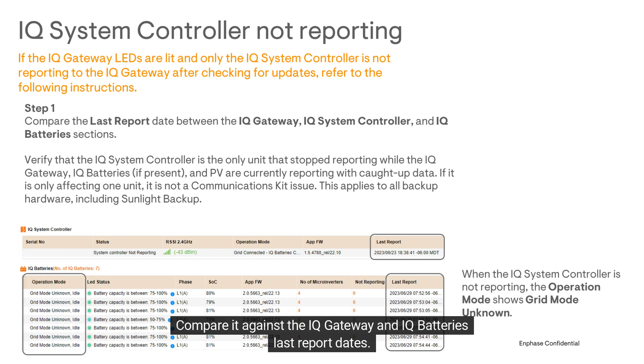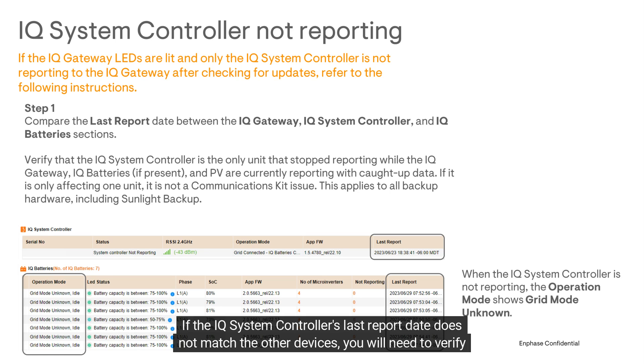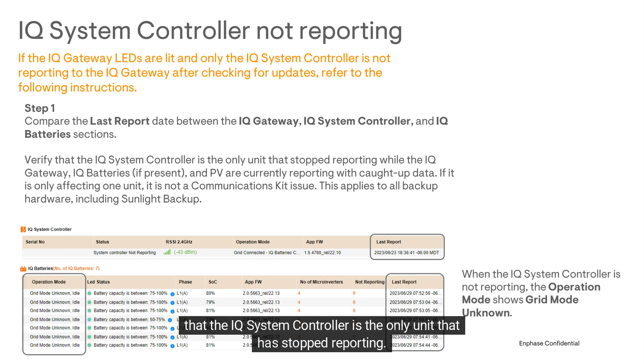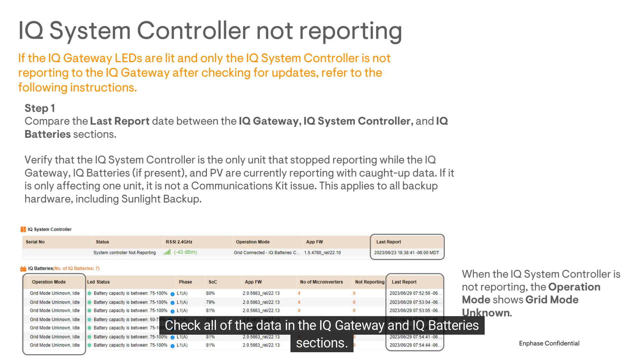Compare it against the IQ gateway and IQ battery's last report dates. If the IQ system controller's last report date does not match the other devices, you will need to verify that the IQ system controller is the only unit that has stopped reporting. Check all of the data in the IQ gateway and IQ battery sections.